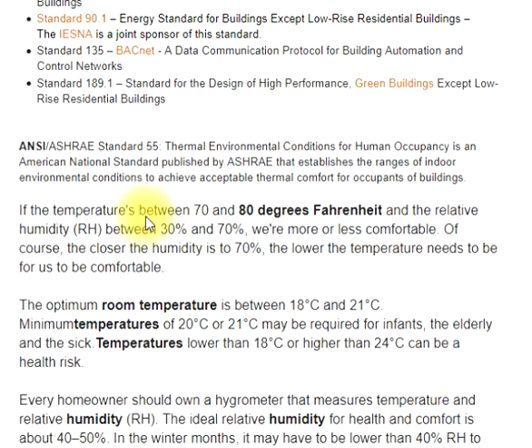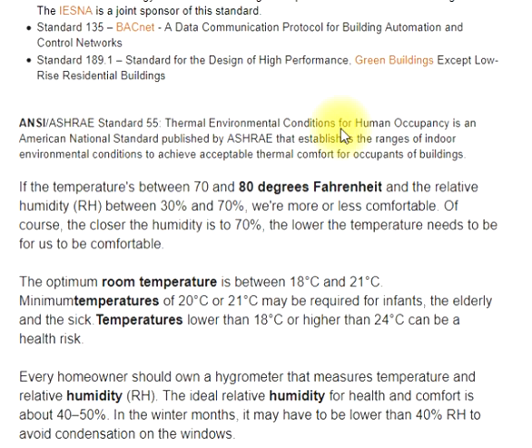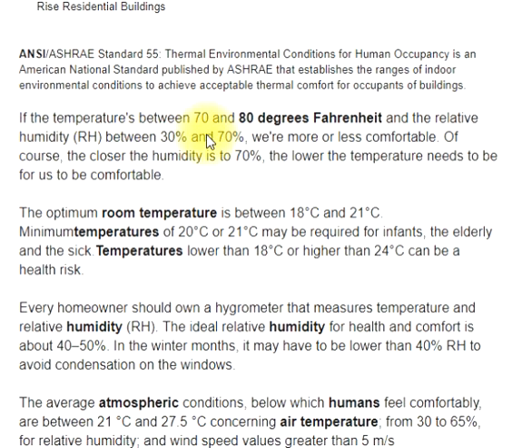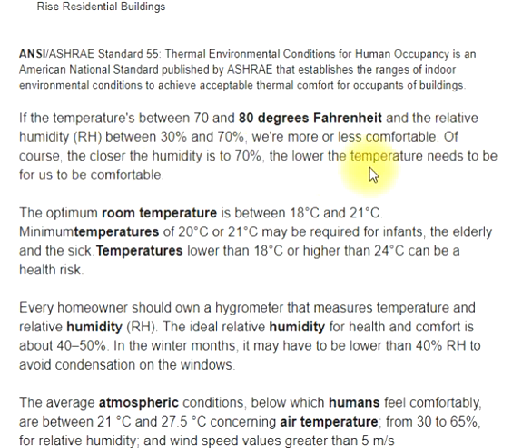ANSI/ASHRAE Standard 55, Thermal Environmental Conditions for Human Occupancy, is an American national standard published by ASHRAE that establishes the ranges of indoor environmental conditions to achieve acceptable thermal comfort for occupants. If temperatures are between 70 and 80 degrees Fahrenheit and relative humidity is between 30% and 70%, we are more or less comfortable. The closer the humidity is to 70%, the lower the temperature needs to be for comfort.